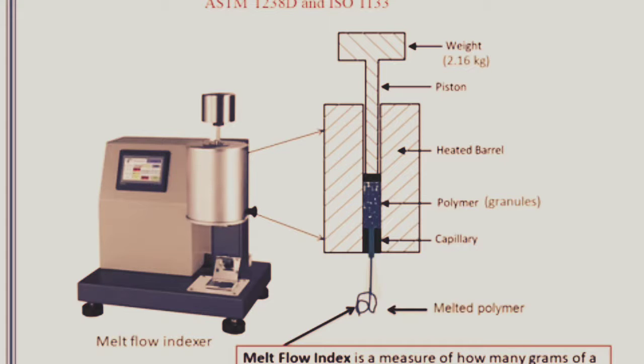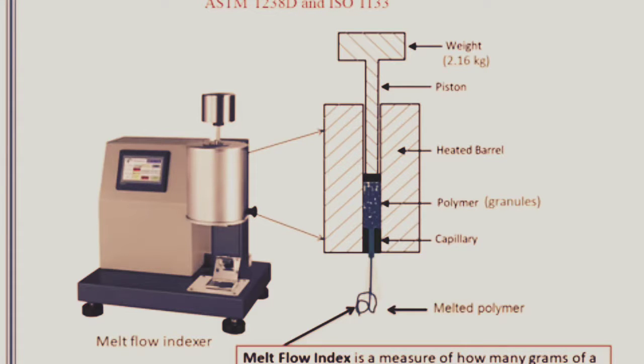First, the barrel is preheated at the desired temperature, then the sample is loaded and allowed to melt for a certain time. The sample should be packed properly inside the barrel to avoid formation of air pockets. After preheating, a 2.16 kg or 5 kg standard weight is introduced onto the piston to apply force. As the weight exerts the force, the material immediately starts to flow. A sample of the melt is collected for 10 minutes and weighed accurately. The weight of the material obtained is the material's MFI value.